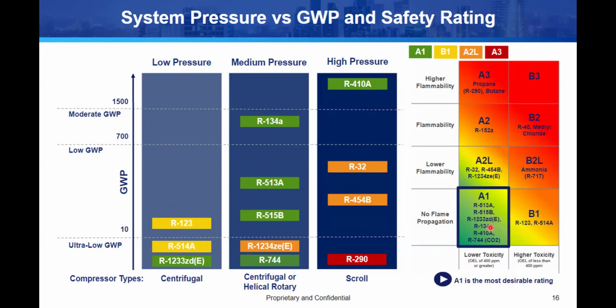There were always 6 boxes in the past. Now there's 8. Previously, on the left side was the A's, the right side was the B's. A meant lower toxicity, B meant higher toxicity. Obviously, we'd like to stay in the A's. Sometimes you can't. Like if we do an ice arena, there might be an ammonia chiller, just the way it goes. Trane for a while had R123 chillers, although that got phased out. But there's been times we've had these toxic refrigerants. There's all kinds of rules associated with that, but it's usually for special projects. We'd like to stay in the A, non-toxic category.